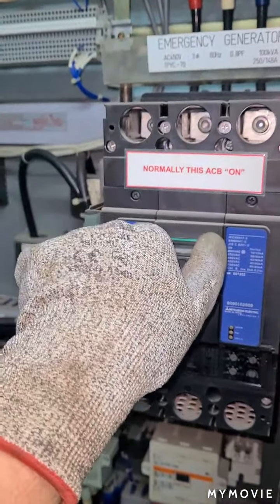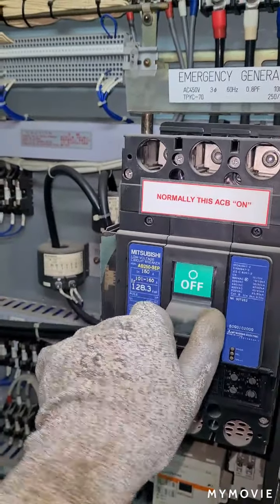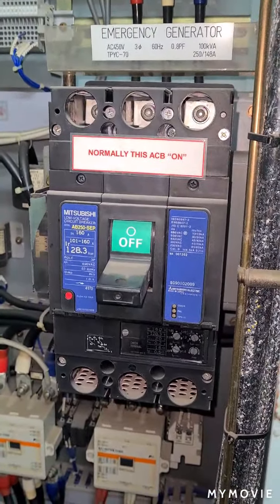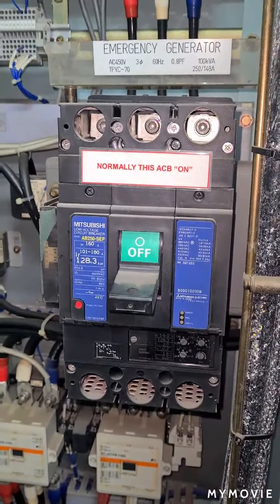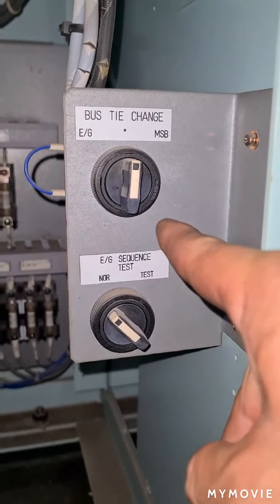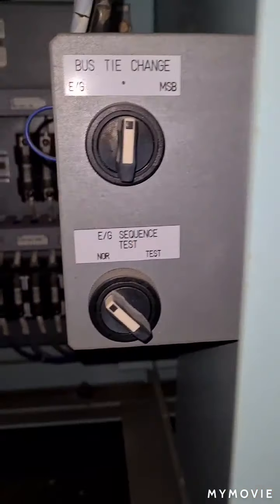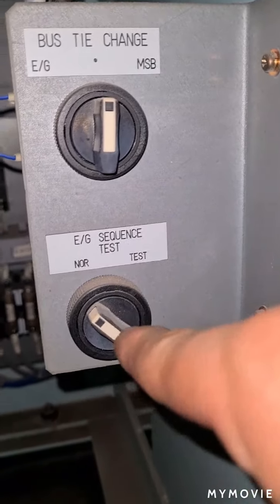When making the breaker of the shore connection, put it normal. Check the circuit breaker rating of the shore and your ship's circuit breaker.